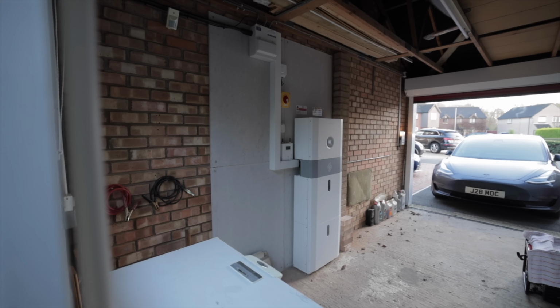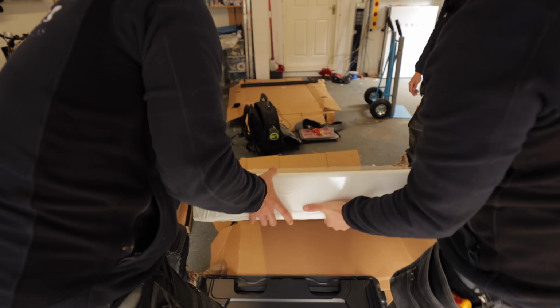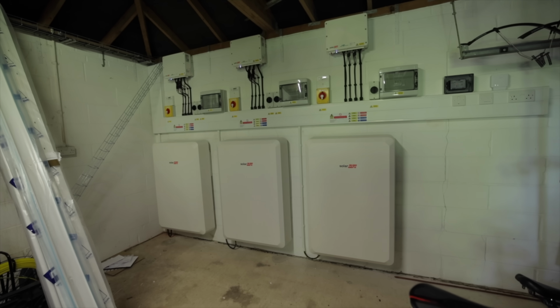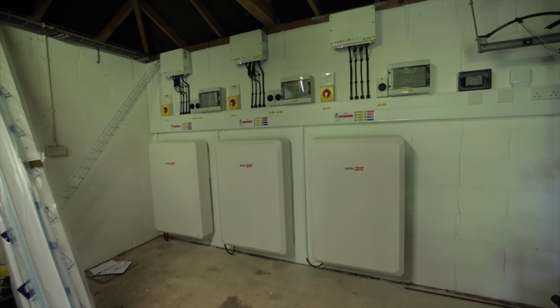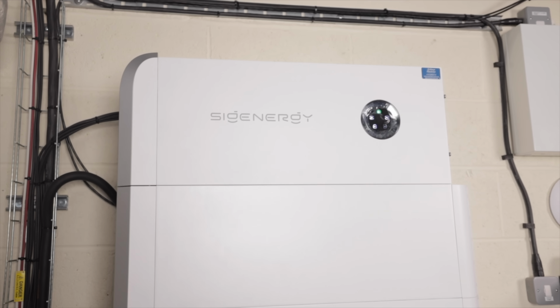If you're thinking about getting backup power, you need to know what level you require. Even with a gateway and a system that switches over instantaneously when the grid cuts out, your system may still not work for you if the inverter isn't sized correctly. This is where most battery systems fail, and it has nothing to do with battery capacity. What do I mean by that?